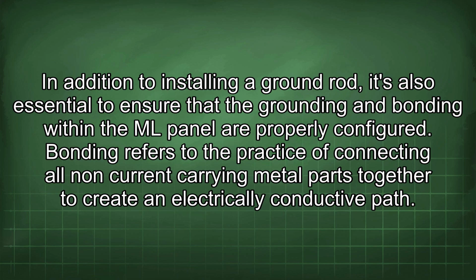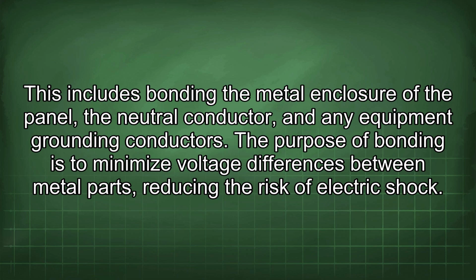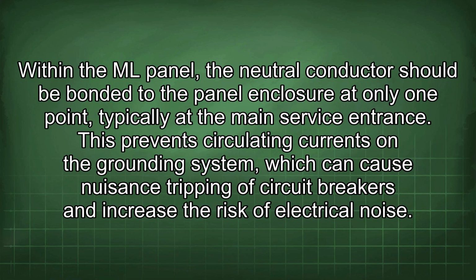panel are properly configured. Bonding refers to the practice of connecting all non-current carrying metal parts together to create an electrically conductive path. This includes bonding the metal enclosure of the panel, the neutral conductor, and any equipment grounding conductors. The purpose of bonding is to minimize voltage differences between metal parts, reducing the risk of electric shock. Within the ML panel, the neutral conductor should be bonded to the panel enclosure at only one point, typically at the main service entrance.